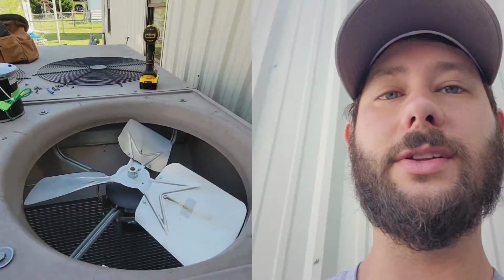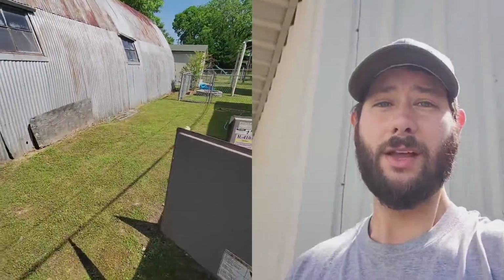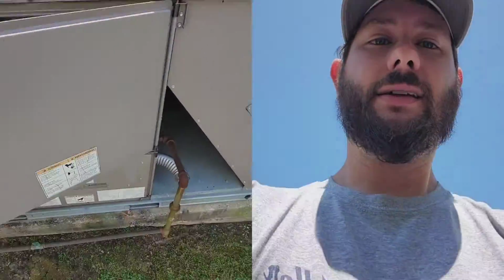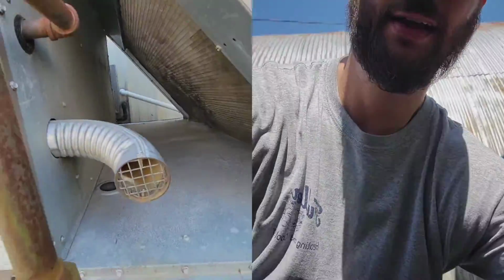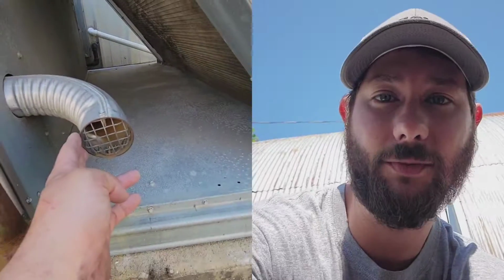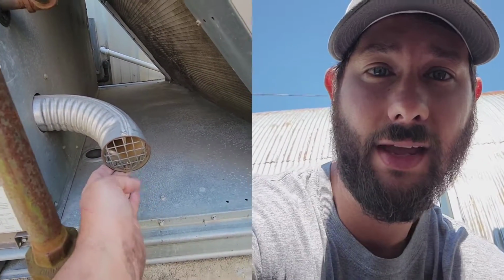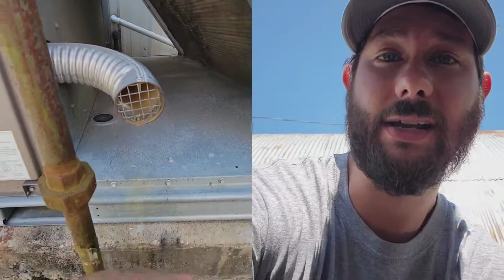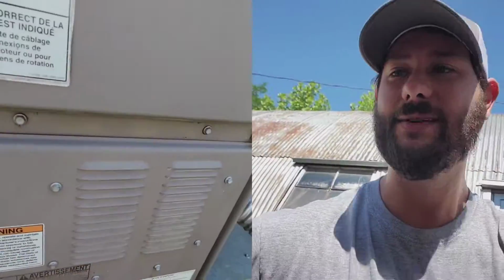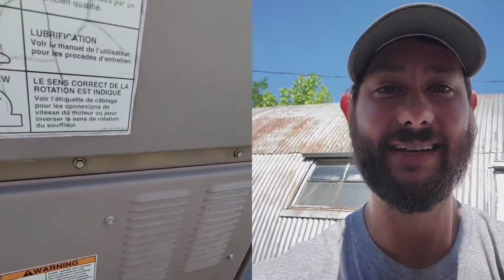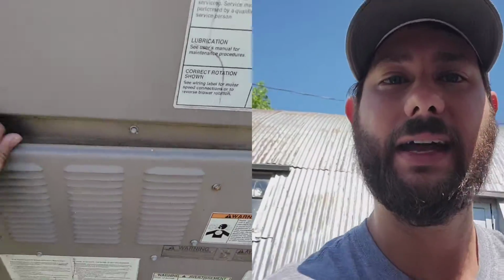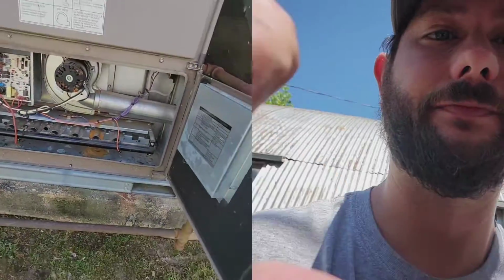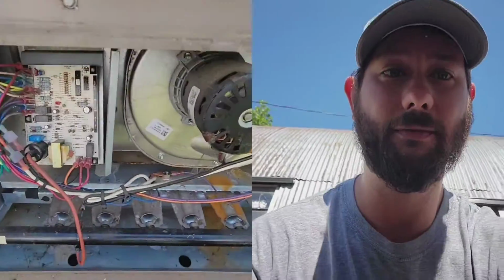And then I'm going to turn this unit back on. We're going to be in good shape. Also, during the heating side of things, this right here is the flue, and that comes from the inducer assembly housing. And this right here, dirt daubers can be in here. I've had wasp nests in there, bird's nest, and that right there can keep the unit from running. We're going to look at the heating section now, talk about more common problems there.